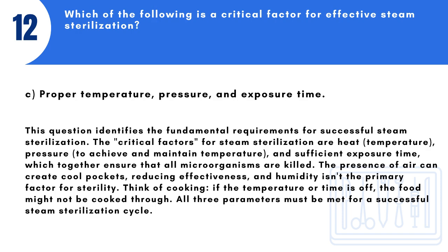Answer: C. Proper temperature, pressure, and exposure time. This question identifies the fundamental requirements for successful steam sterilization. The critical factors for steam sterilization are heat, temperature, pressure, to achieve and maintain temperature, and sufficient exposure time, which together ensure that all microorganisms are killed.